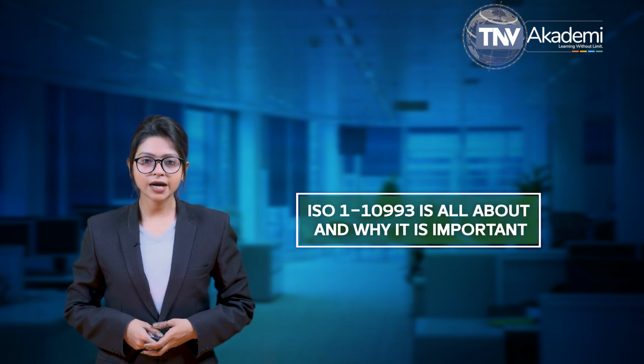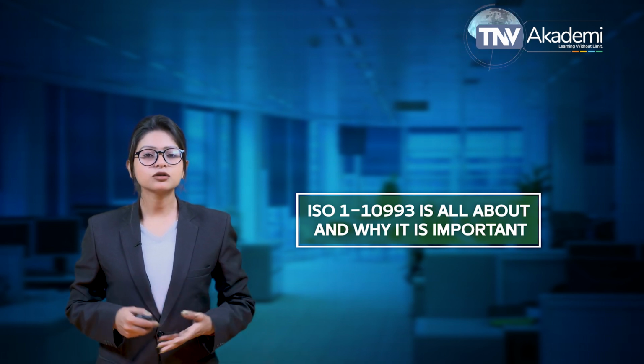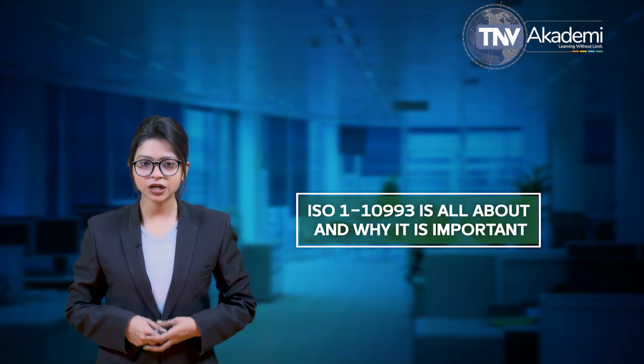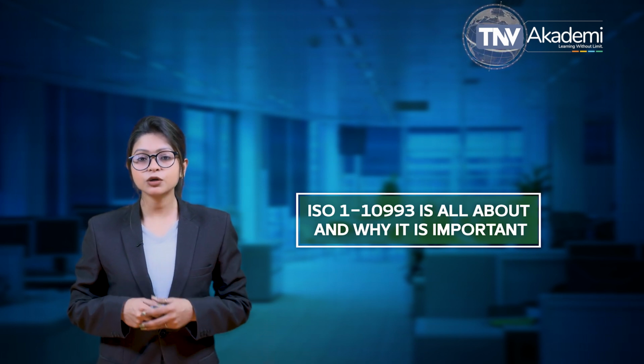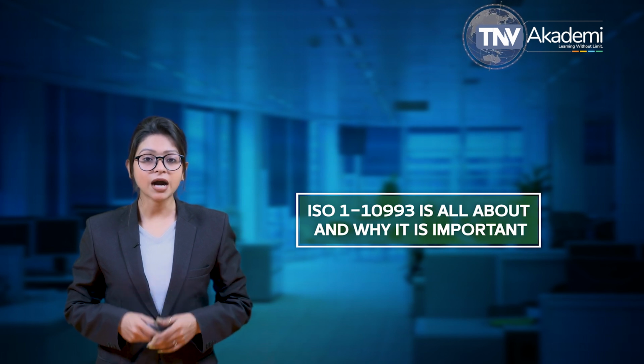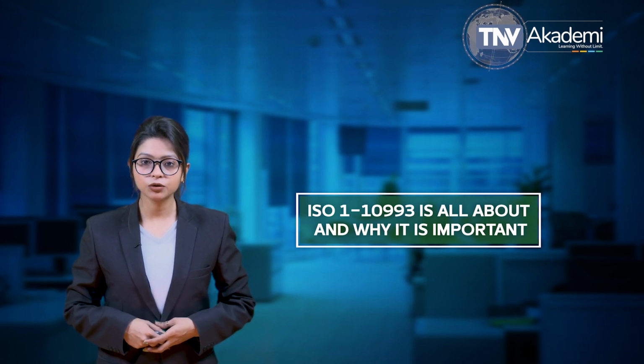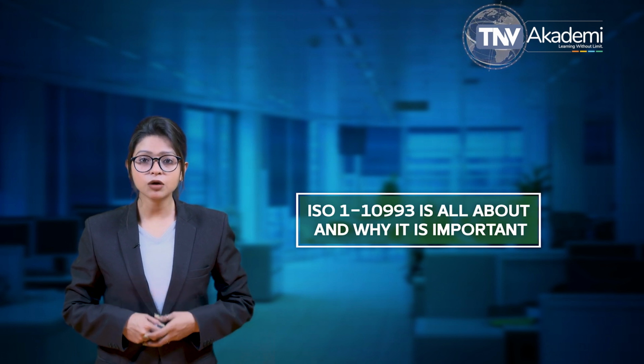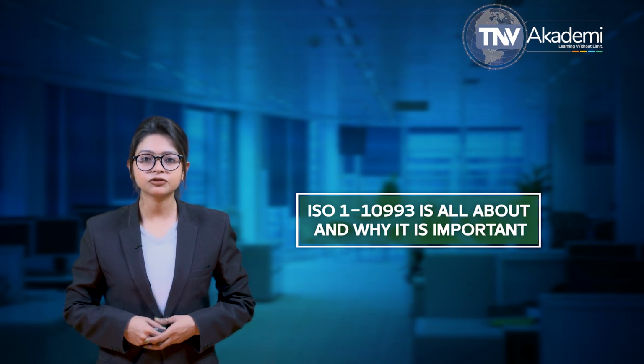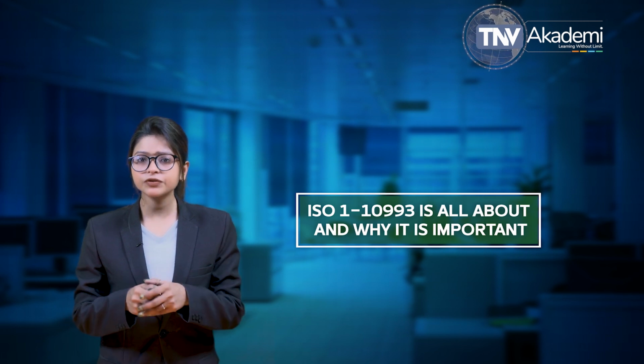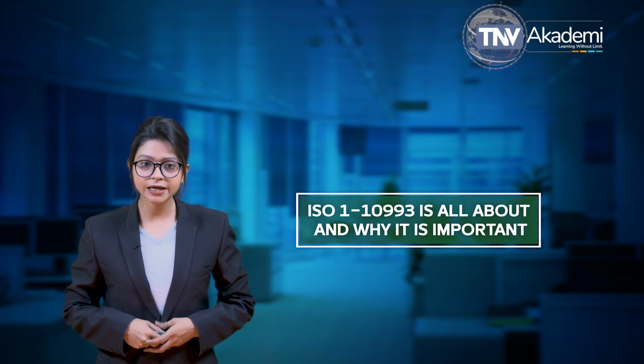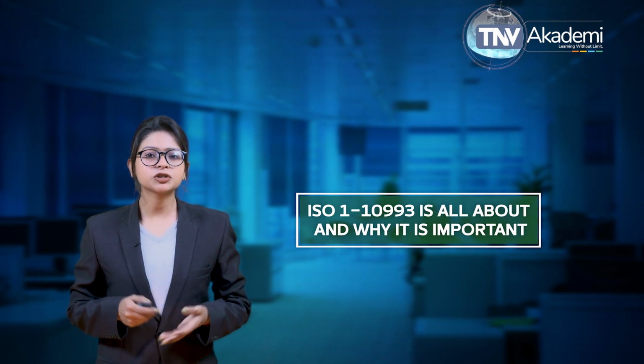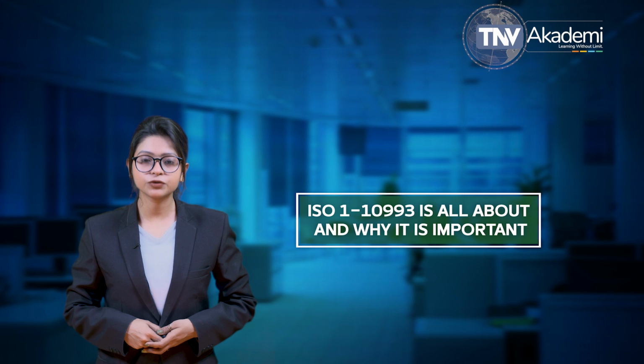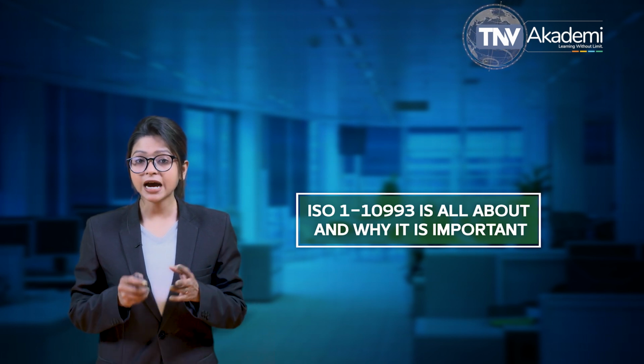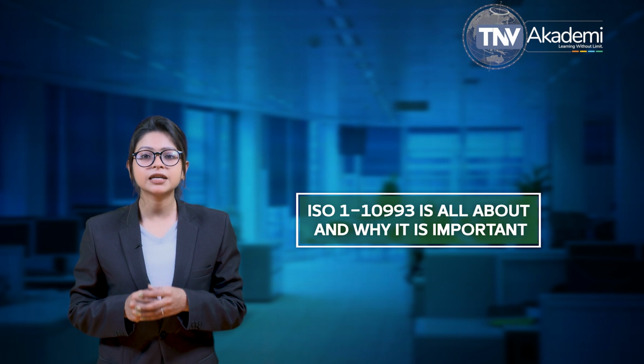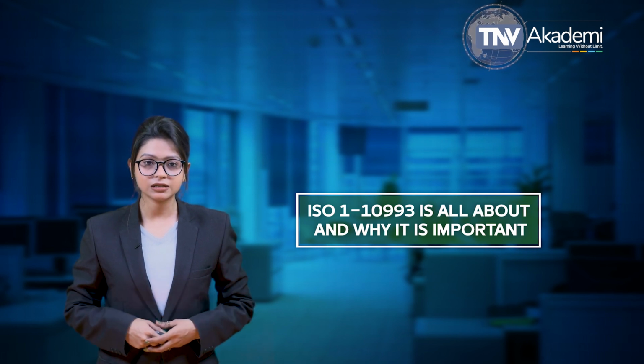Why is ISO 10993-1 important? While ISO 10993-1 sets the stage and the remaining parts of ISO 10993 dig into the details, part 1 should by no means be overlooked. This is because the 2018 update of ISO 10993-1 indicates a significant shift in the approach to supporting preclinical medical device safety. Instead of a checklist-based approach, the standard moved towards a risk-based approach that starts with understanding the materials and the chemical constituents in those materials.